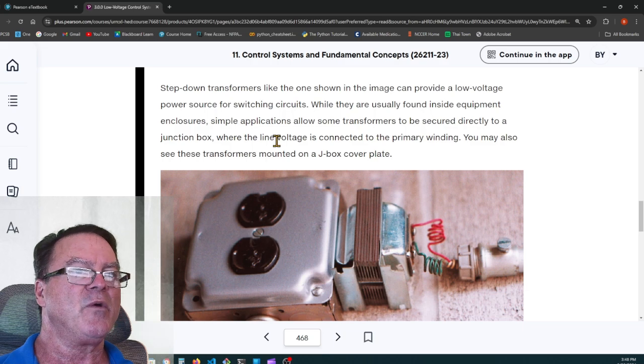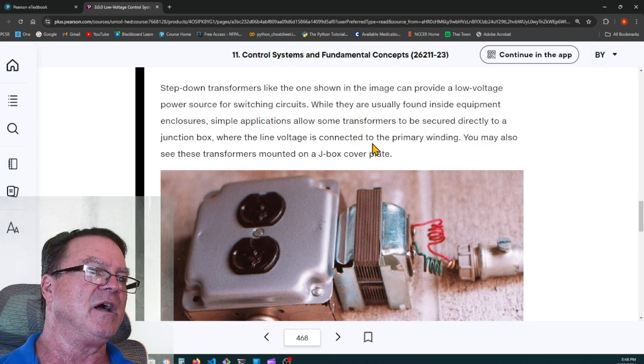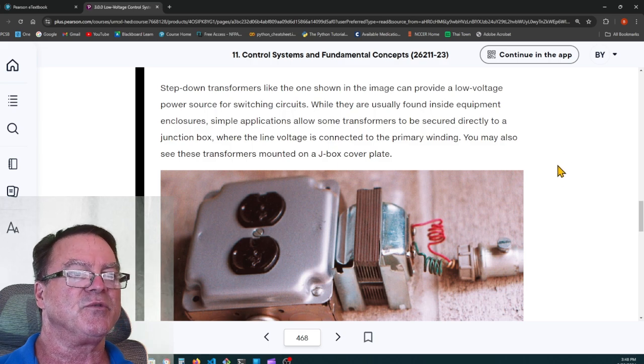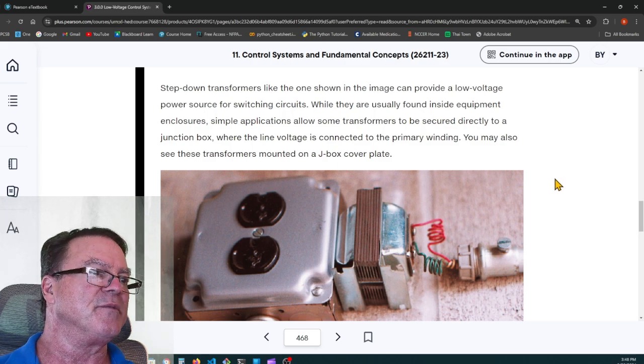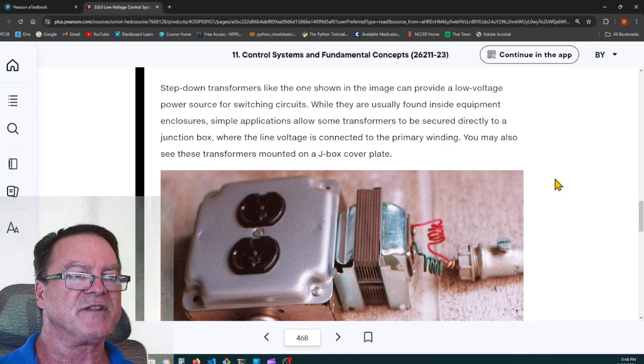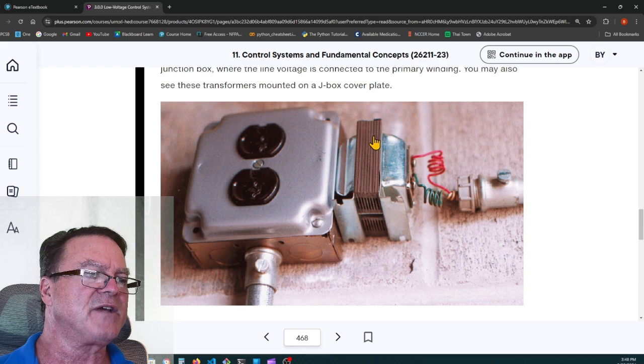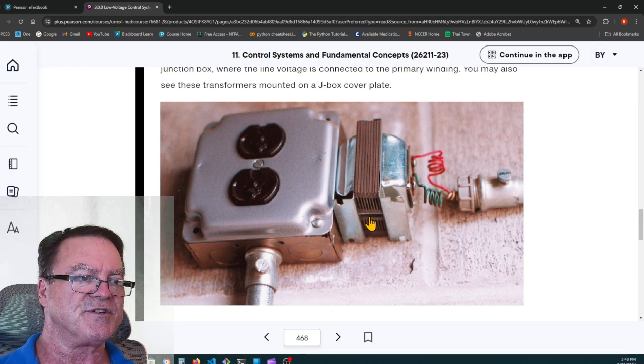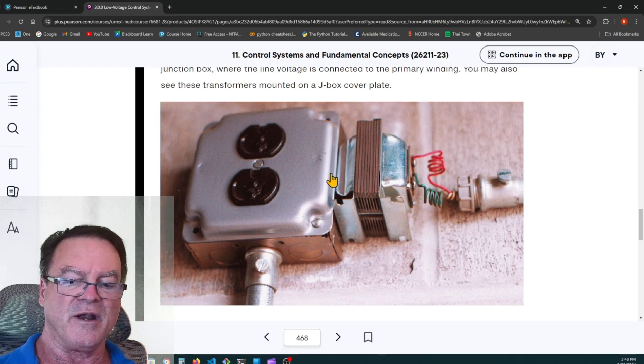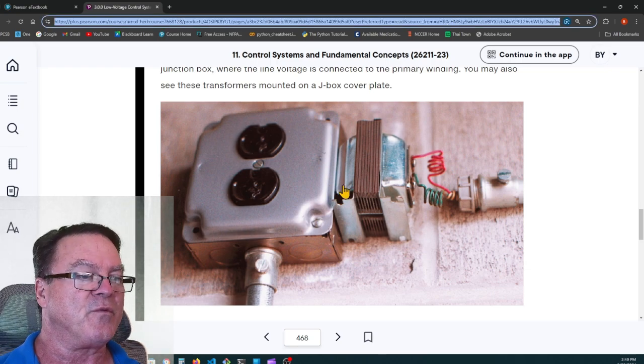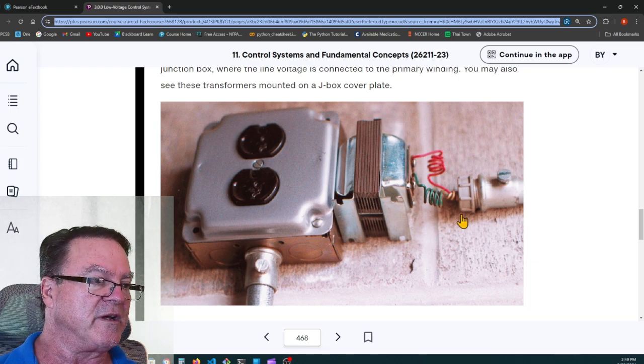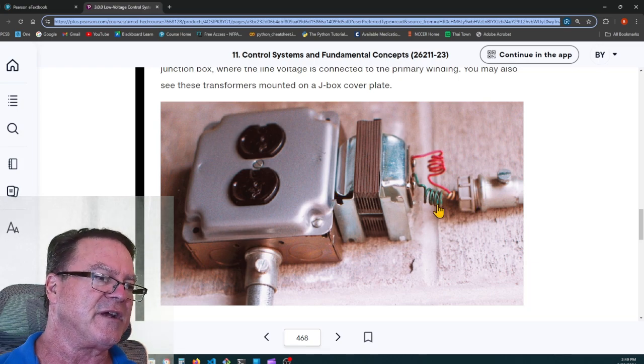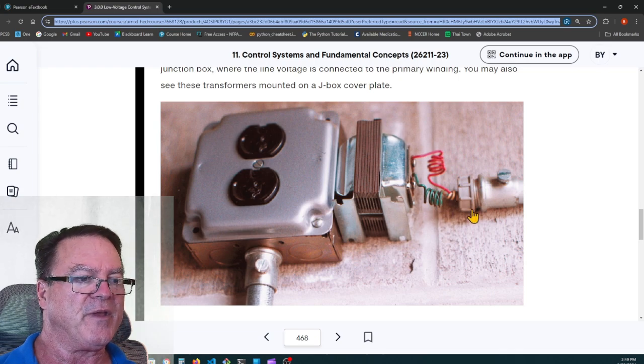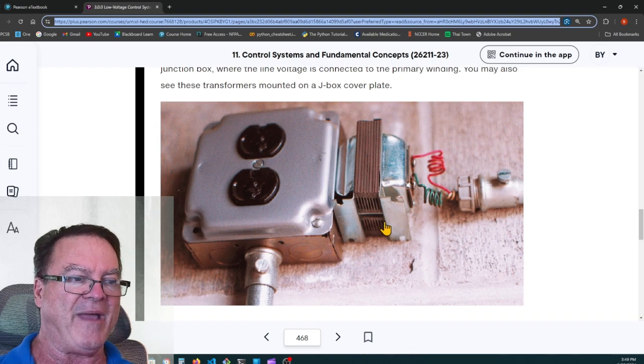While they're usually found inside equipment enclosures, some simple applications allow some transformers to be secured directly to a junction box where the line voltage is connected to the primary winding. You may also see these transformers mounted on J-box cover plate. You'll see this a lot of times for doorbells, where they have low voltage systems for doorbells. They'll knock a knockout out and just mount the transformer right on the side of the box, and then the low voltage wiring comes out. They try to protect it as well as possible, the low voltage wiring. So it's usually done either up in the top of a closet or at the panel in the garage.